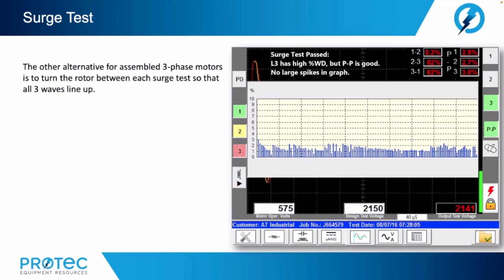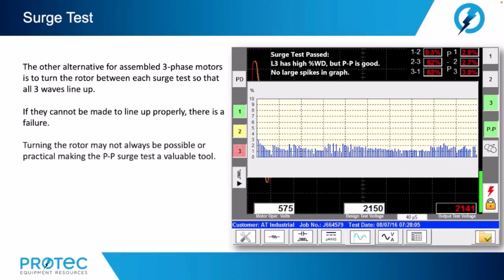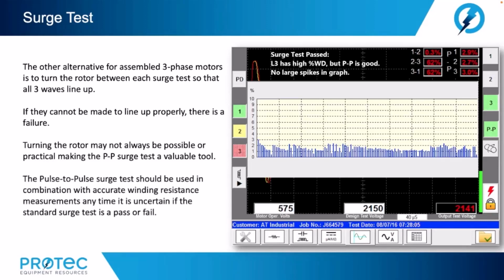The other alternative for assembled three-phase motors is to turn the rotor between each surge test so that all three waves line up. If they cannot be made to line up properly, there is a failure. Turning the rotor may not always be possible or practical, making the P2P surge test a very valuable tool. The pulse-to-pulse surge test should be used in combination with accurate winding resistance measurements anytime it is uncertain if the standard surge test is a pass or a fail.